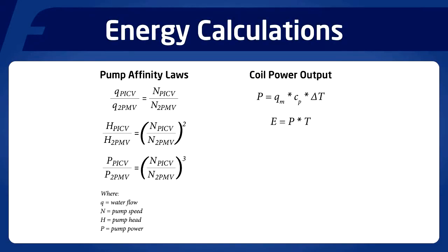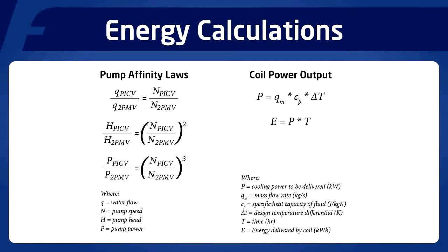It is possible to use the pump affinity laws and the coil power output equation to compare the energy performance of the air handling unit when fitted with a pressure independent control valve and a conventional two-port modulating valve. In particular, we know that the change in pump power is proportional to the cube of the change in pump speed, and we know that the cooling power to be delivered by a coil equals the mass flow rate multiplied by the specific heat capacity of the fluid and the delta T of the supply and return water.